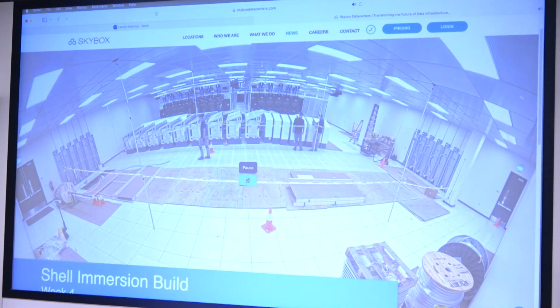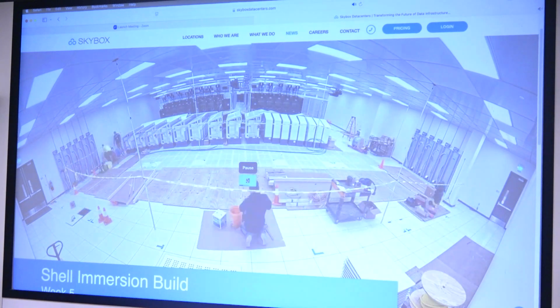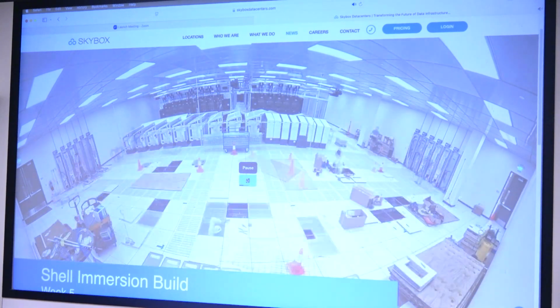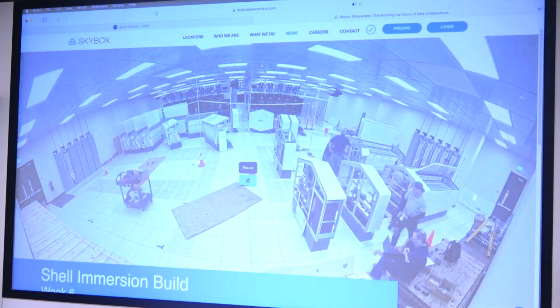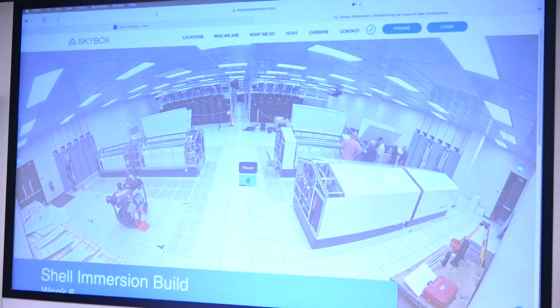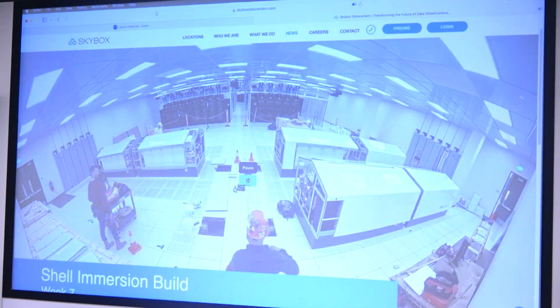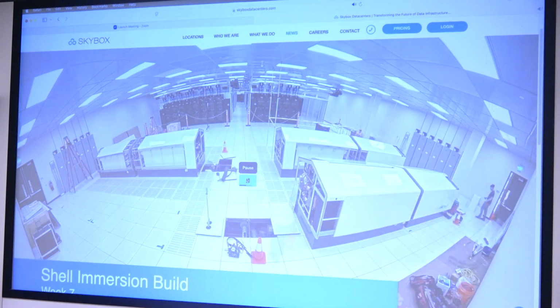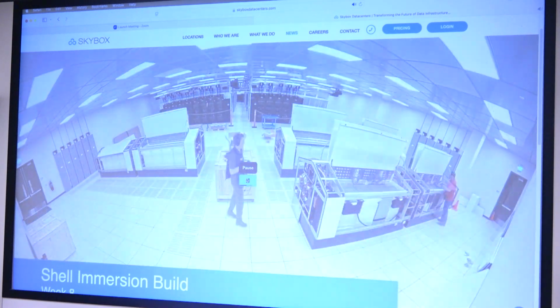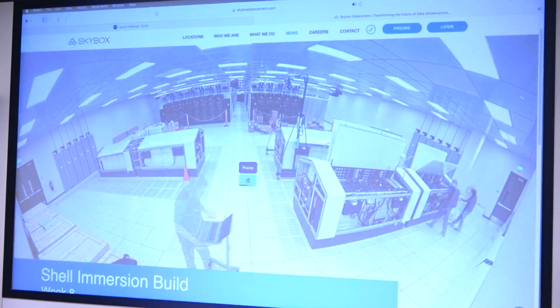This is the preparation underfloor primary fluid network. The whole room has a water pipe going around, so it's connected at both ends. If you have to shut one down, you still have water coming from the other end. We've got the tanks arriving in back being set up. You'll see really quickly all the compute nodes will be dunked in and cabled up in just a second. There you go on the right. Got the PDUs along the back wall.